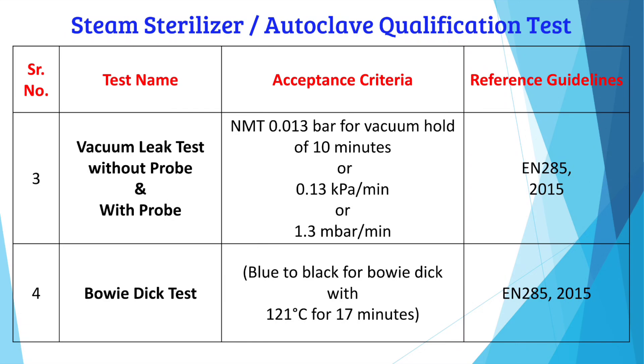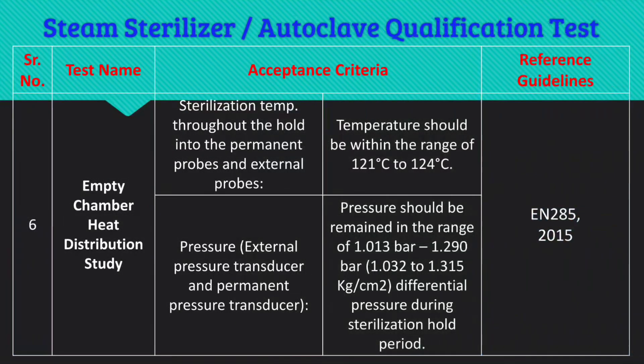The Bowie-Dick test is used to verify that air is removed from the chamber. The acceptance criteria for the Bowie-Dick test is a color change from blue to black at 121°C for 17 minutes. The specific color change is not specified in any guidelines and depends on the supplier or vendor. The reference guideline for this test is EN 285:2015.